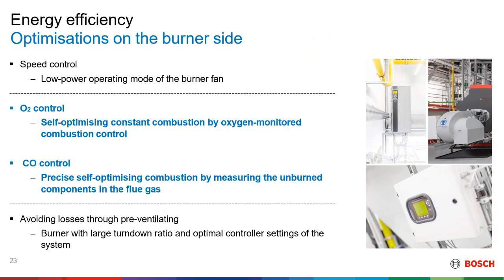So the second part is O2 and CO control. O2 control will be a probe installed on the flue gas on the exhaust side of the boiler, and this will monitor the amount of oxygen or excess oxygen that you have in the flue gas. Going back to the first topic, where we had the formula for calculating losses on the flue gas, as you saw, having excess oxygen increases the amount of flue gas losses. So the O2 control will limit the amount of excess oxygen.